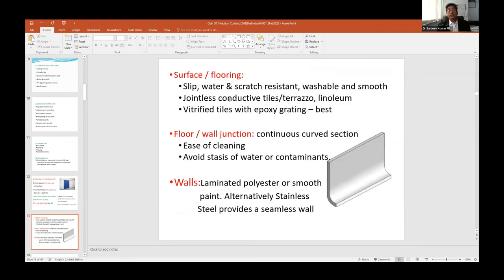We have to take care of the surface and flooring. The flooring should be slip, water, and scratch resistant, washable, smooth, and jointless—if tiles, it should be jointless conductive tiles or linoleum flooring. If vitrified tiles are used, they should have epoxy grouting, which is considered best.